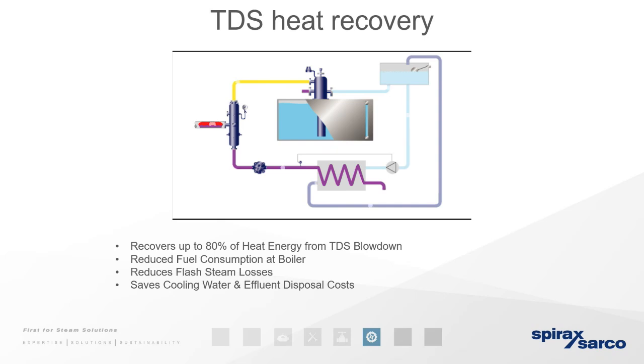Okay. So again, we're talking about heat recovery here. Alvin touched upon the importance of it as well. We want to make your system as efficient as possible, and the best way to do that, in this particular case, is by raising the heat of the water you're supplying to your boiler. So here we've got the TDS recovery. Your TDS is being blown down, then it goes through a trap, which separates the steam and the condensate. We run it through a heat exchanger and use that to preheat the water that's then being fed into the boiler.